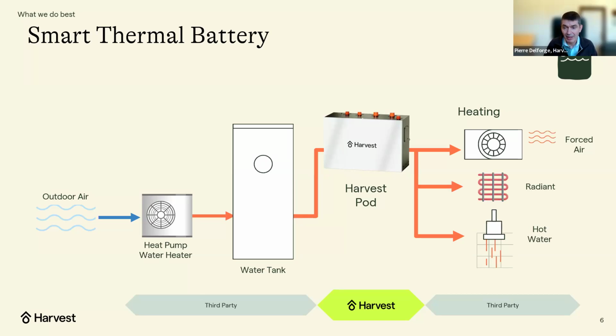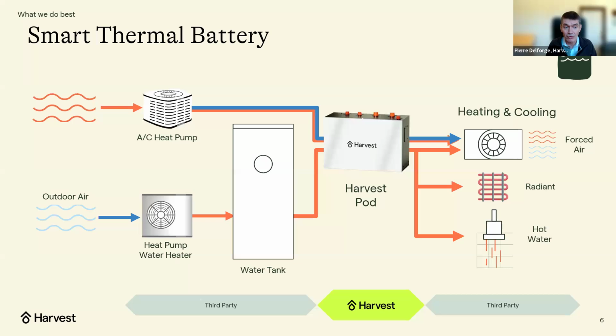And just like Edward said, the CO2 heat pump only does heating, not cooling. So what we do is we integrate with either existing or new ACs or heat pumps to provide cooling. If you have a heat pump, then you can use that for supplemental heat as well to supplement the hydronic system. So you can go up to 4 tons of heating capacity, even though the SanCO2 heat pump itself can only go up to 2 tons with thermal storage by itself.